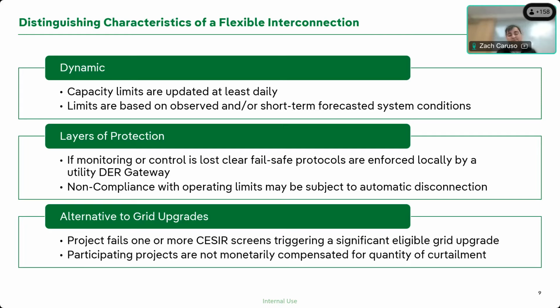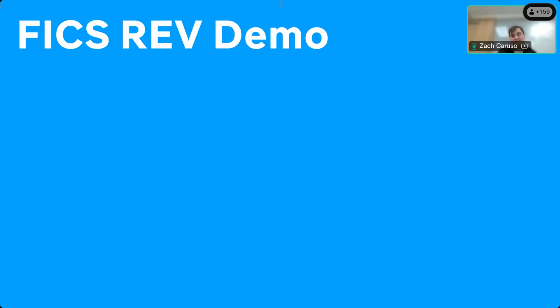And that's the compensation, or the value stream, that is received by that customer when they agree to the flexible interconnection. It is that deferral of grid upgrades that they don't have to pay for. Because in New York, it's very much a cost causer, cost triggerer pays. And that is why we do not pay for curtailment in New York under a flexible scheme, because you're agreeing to a flexible scheme as a condition for interconnection. So you're agreeing that you're causing this problem and you're being curtailed to mitigate it. All that is to say, that's just background. Now to talk about the fun stuff.